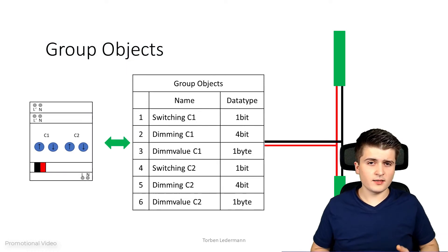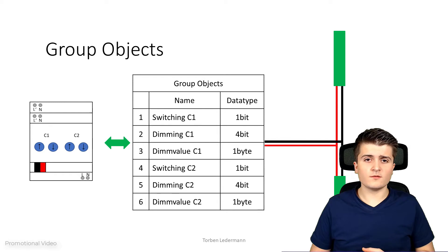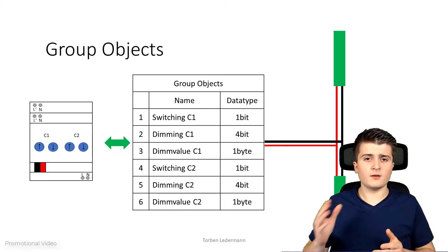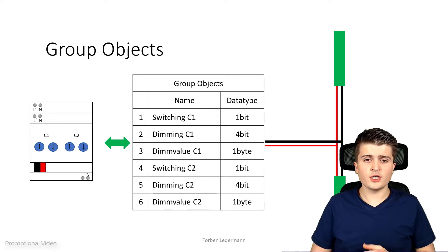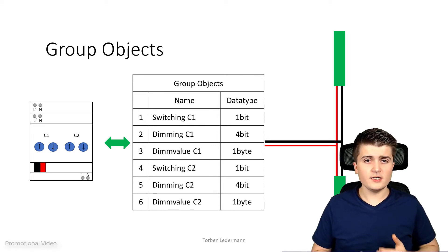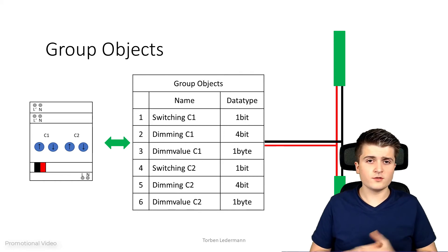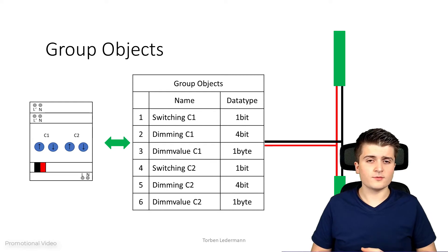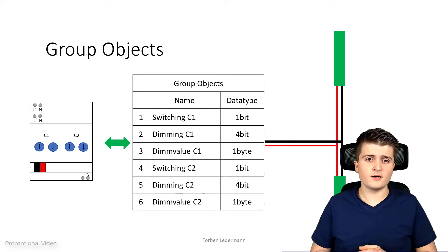This may sound more complicated than it really is. Here we have the example of a dimming actuator with two dimming outputs. As you can see, we have the group object in the middle between the bus wire and the bus device. For each channel we now have multiple group objects, each for their own function. First of all, we have a group object for switching channel one or two on and off. Then we have a group object for dimming channel one or two. And we also have a group object for the dim value, where we can specify a value and the dimming actuator turns the light to that specified value.